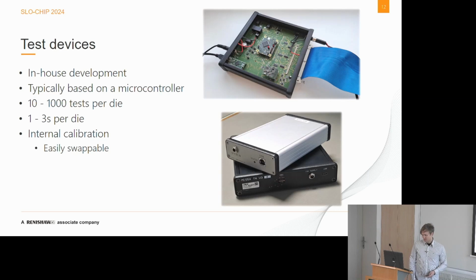The test devices are connected to a probe card, so pieces of electronic equipment which perform some tests to determine if your die is suitable or not. We develop these in-house, typically around a microcontroller. Per each die, we usually perform from 10 to 1,000 tests, and typically this takes up to 3 seconds. We also perform calibrations of these devices and store the data inside, meaning that these are easily swappable. If something goes wrong, we can just swap them with little or no downtime.